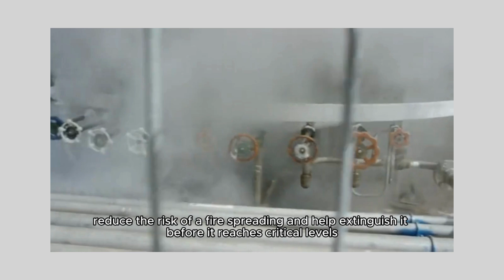4. Automated fire suppression systems. Beyond traditional sprinklers, advanced fire suppression systems that can automatically detect and extinguish fires in high-rise buildings are a major step forward. These systems utilize smoke detectors and heat sensors to activate suppression systems at an early stage. For example, water mist systems or gaseous fire suppression systems that use clean agents such as FM200 or Inergen could provide an effective alternative in areas where water-based sprinklers might cause significant damage, such as data centers or electrical rooms.